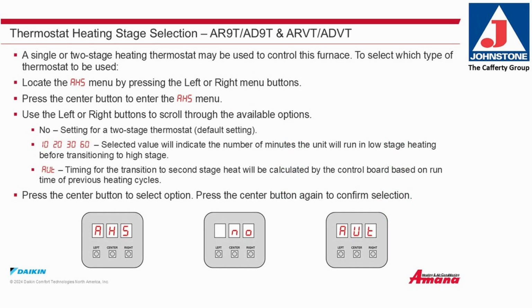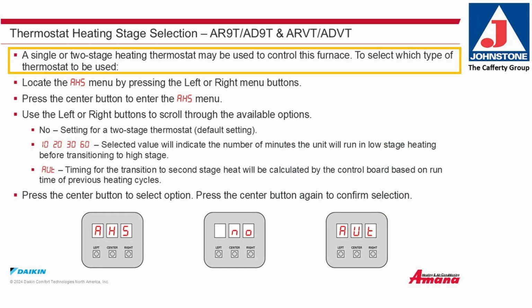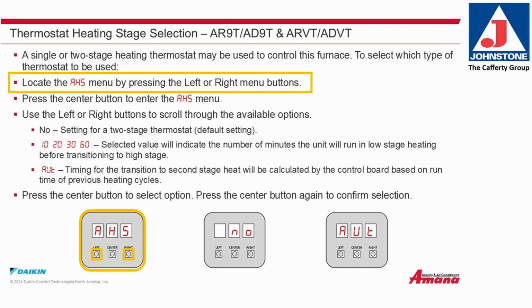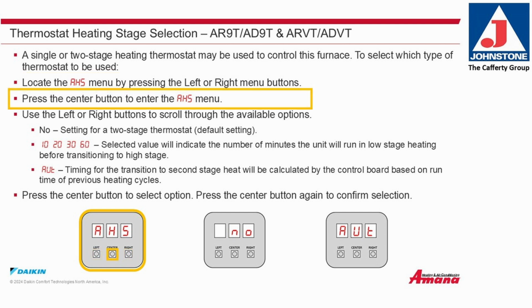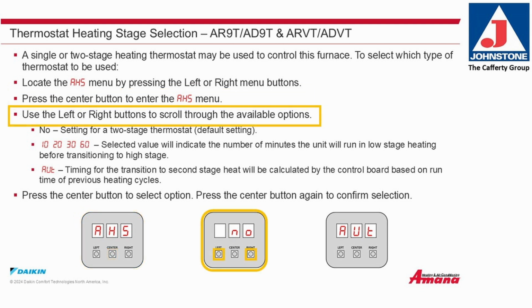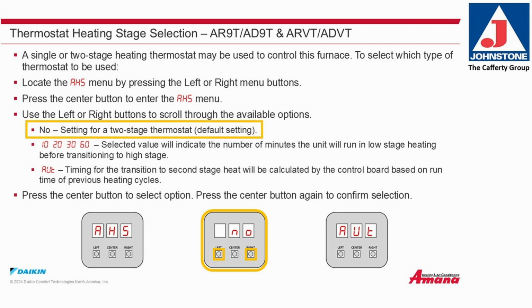Thermostat heating stage selection. A single or a 2-stage heating thermostat can be used to control this furnace. To select which type of thermostat to be used, locate the AHS menu by pressing the left or right menu buttons. Press the center button to enter the AHS menu. Use the left or right buttons to scroll through the available options. NO setting is the default setting for a 2-stage thermostat.